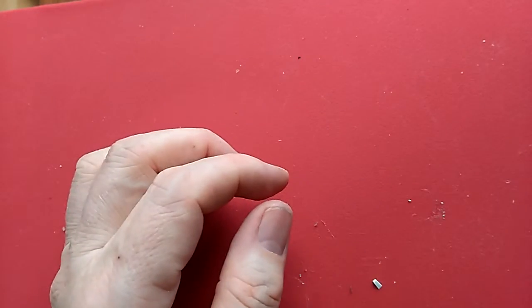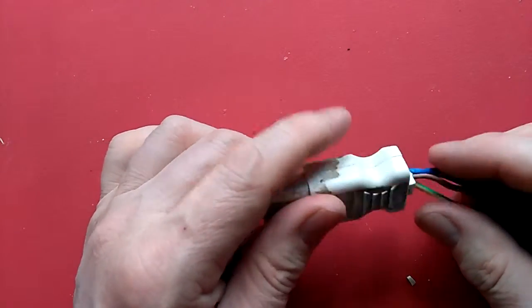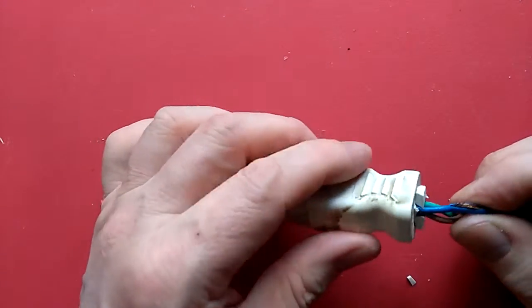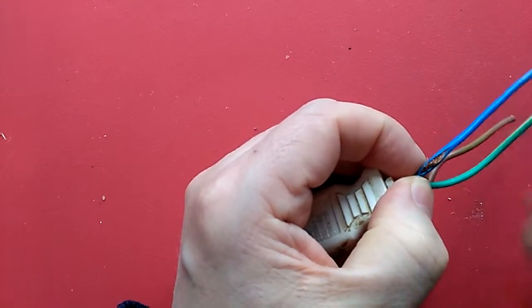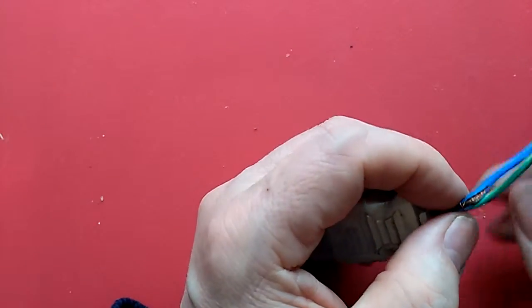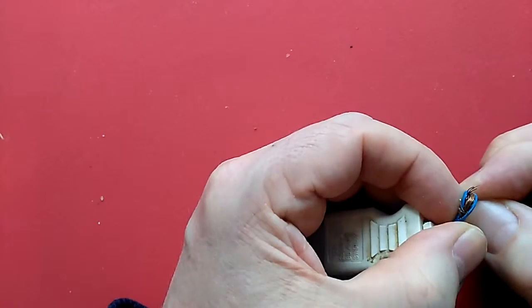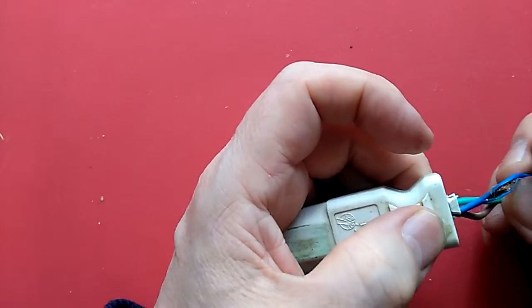Here's what I found - yes, it is disgustingly filthy, but there it is anyway. You can see the problem. I sliced this open with a knife, so this wasn't sliced open originally, but what was happening is that a number of these copper strands in the neutral - the others are fine for some reason - had begun to split away.